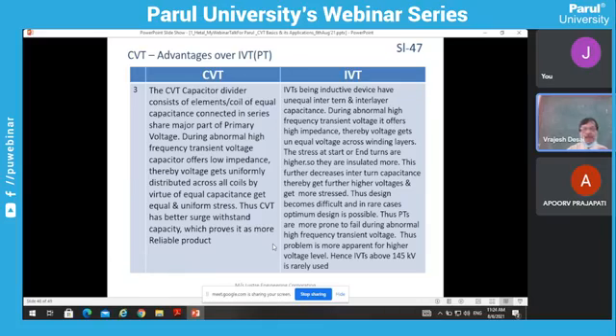Contrary to this, the IVT is an inductive component. There is a big number of turns provided, so we have unequal interturn and interlayer capacitance. Also, during a high frequency surge, being an inductive circuit, it offers very high impedance. So it establishes a non-uniform electric field, and because of the non-uniform capacitance, the first and last turns of the PT get higher voltages. So it may tend to fail. The manufacturer will provide higher insulation on the beginning and last turns. But when you provide higher insulation, the interlayer capacitance reduces, and when capacitance reduces, the voltage is higher. So there is no end to this.